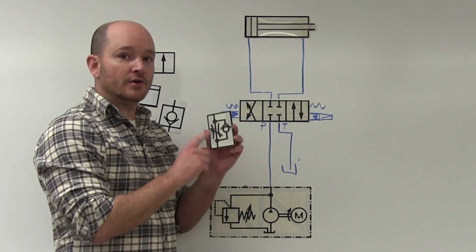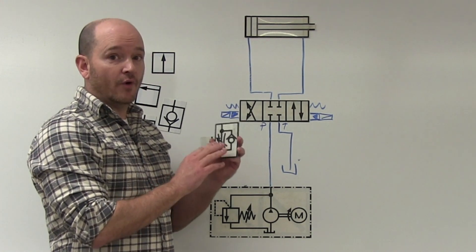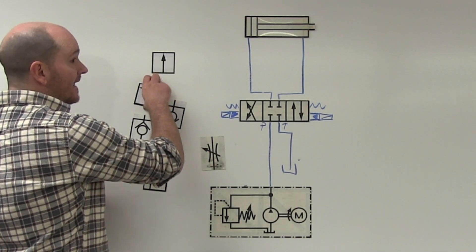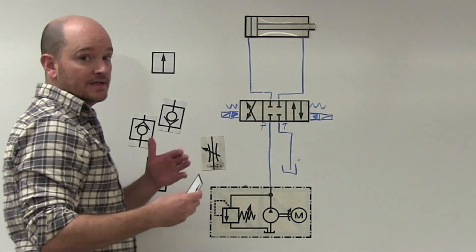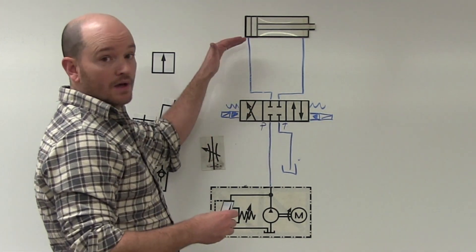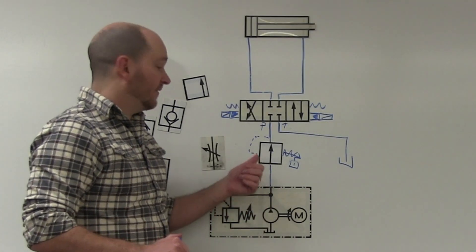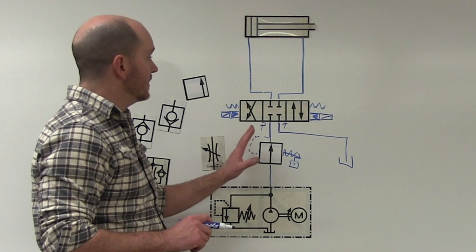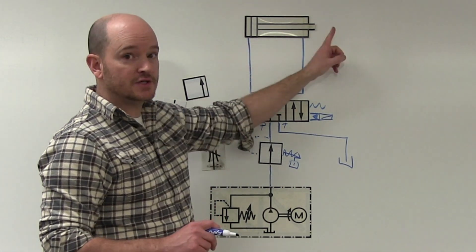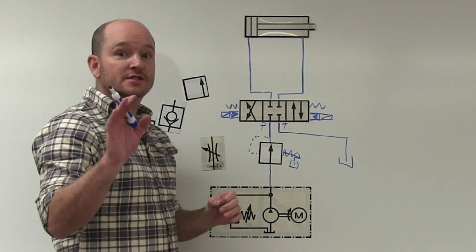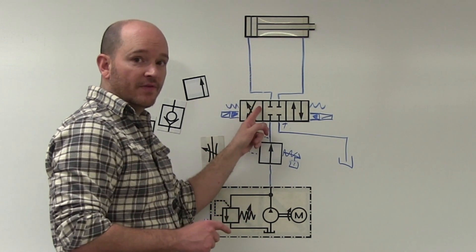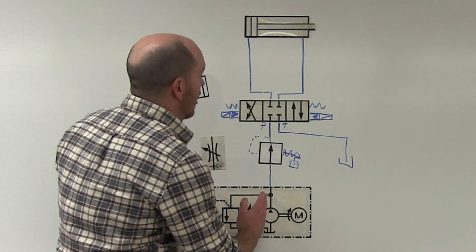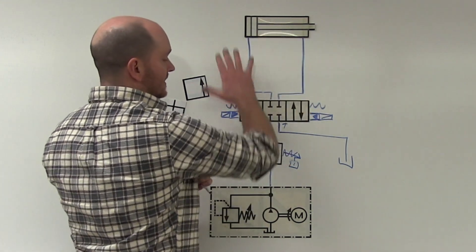And people often stop at that point and think they understand a bypass check valve. But bypass check valves aren't just used for flow control valves. They can be used for any pressure control valve that may need to be placed above the directional control valve. Here's an example of a pressure reducing valve. The pressure reducing valve here is going to reduce pressure on both extension and retraction. And so we would want to put this before the directional control valve, because it will control the pressure for all of the fluid going into this system.